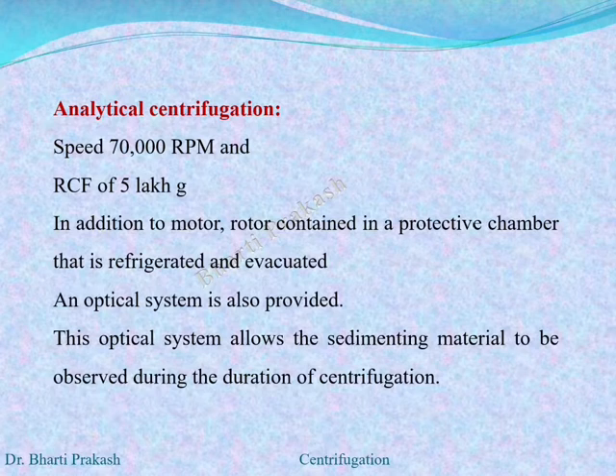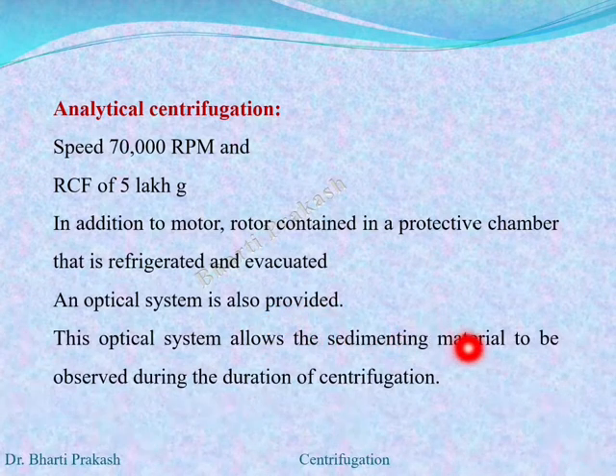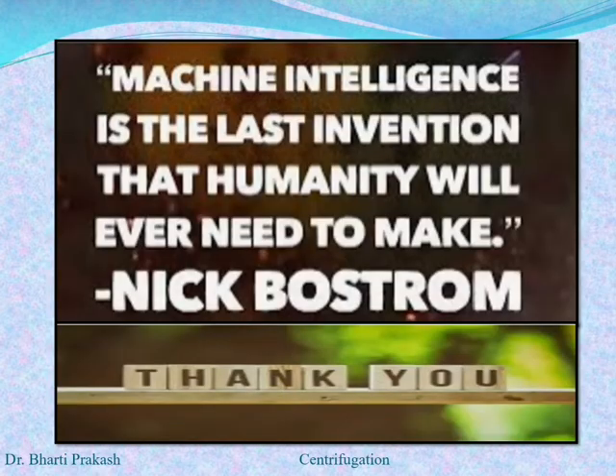The second type of ultra centrifugation is analytical centrifugation. In this, the speed is about 70000 rpm with an RCF of 5 lakh g. In addition to the motor, the rotor is contained in a protective chamber that is refrigerated and evacuated. An optical system is also provided which allows the sedimenting material to be observed during centrifugation. The optical system is of three types: the light absorption system, the schlieren system, and the Rayleigh interferometric system. Preparative and analytical centrifugation will be studied in the coming lectures.